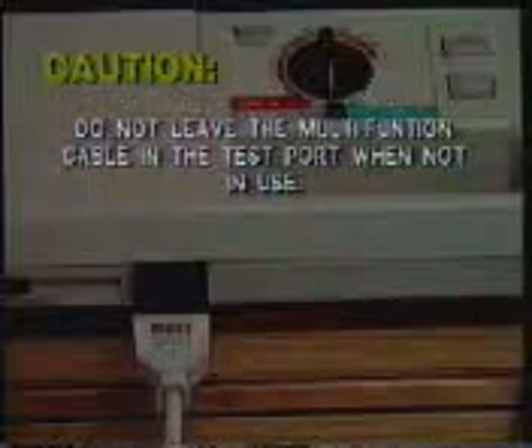To test the PD-1200 defibrillator capacity, insert the end of the multifunction cable in the receptacle at the left front of the device. Choose the 200 joule setting, charge and discharge into the machine by simultaneously depressing both buttons on the cable. The Test OK message will appear on the screen, and a 15-second ECG strip will print out. Caution: do not leave the multifunction cable in the test port when not in use.